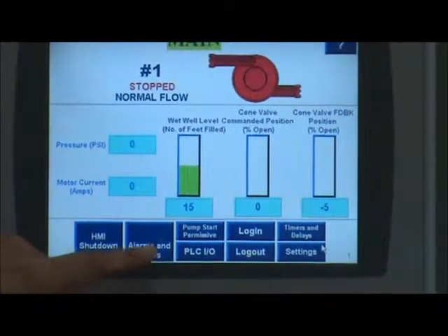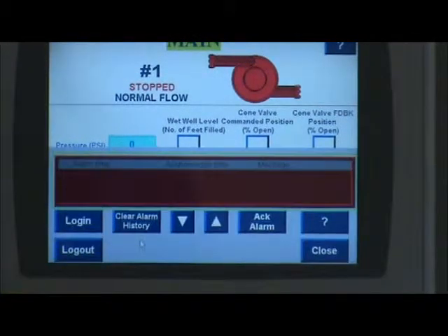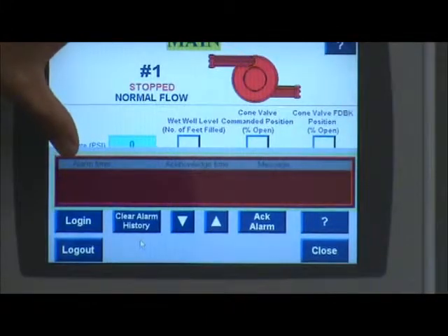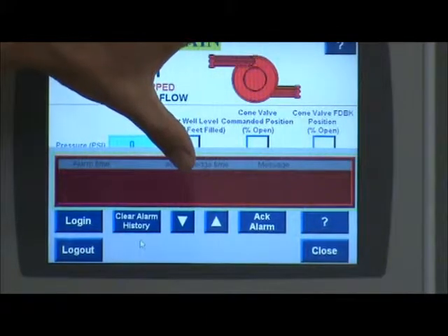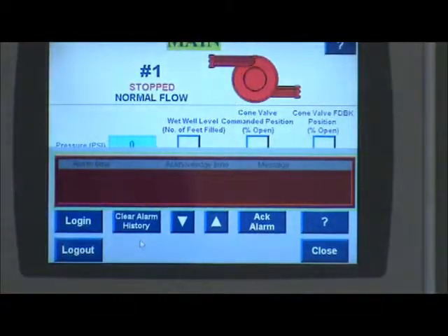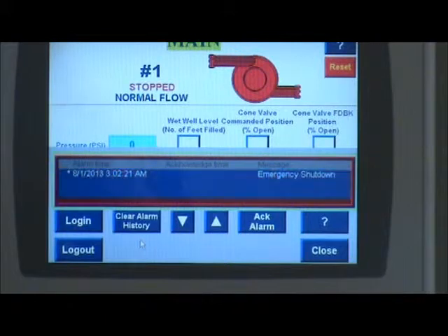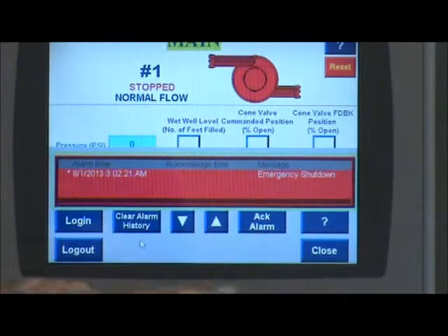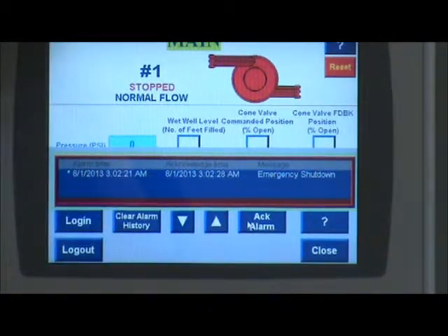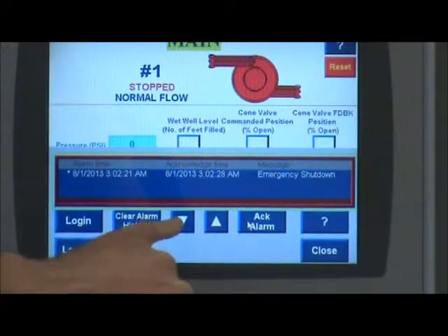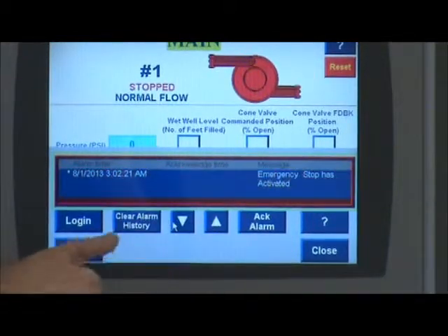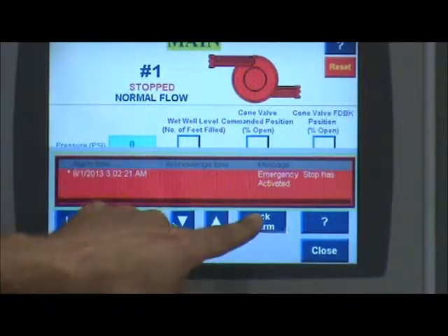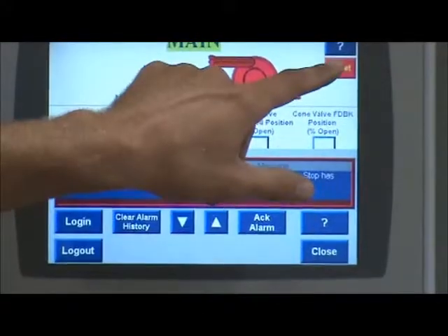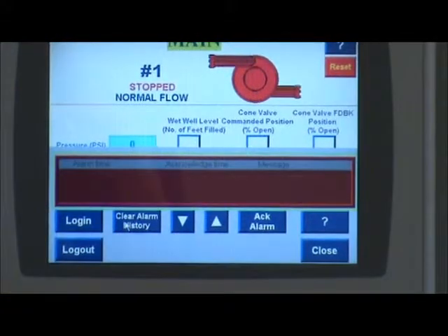Our first navigation key is our alarm and fault. When you push that, it comes up. It shows you an alarm time, the acknowledgement time, and then it displays what the actual fault is. So I'm going to create one real quick. And today at 3, we had an emergency shutdown. I will acknowledge it. And that time comes up to display that. And you can cycle through all the alarms with the up-down arrows. And then after you acknowledge the alarm, you reset it, and you can clear the history.